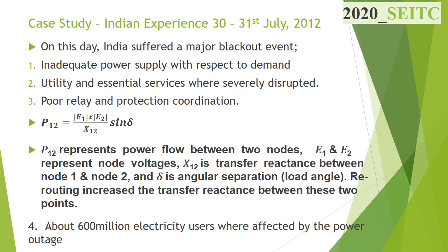This can be understood better from a simple power angle equation as shown. Also, sine being an increasing function, for transfer of an equal amount of power between two points with increased transfer reactance, the value of delta has to go up. This implies that the rotors of the northern region machines will further fall behind the rotors of the western region machines. This gave rise to a phenomenon known as power swings, and impedance relays could not differentiate between power swing and a fault condition, hence initiating a trip action.